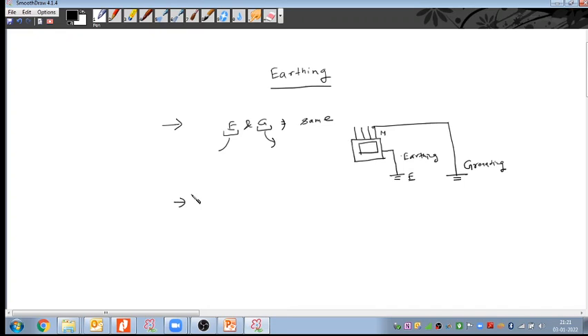Secondly, grounding, in my opinion, is what we refer to when some sort of fault occurs. For example, if any machinery, panel or motor has leakage current, or some other unwanted or unbalanced type of fault happens, then we refer to it as grounded or earth leakage ground, or neutral ground resistance. As you said, in the case of a transformer we connect a resistor of some optimum value to the neutral point. So grounding basically refers to unwanted things like fault, leakage current, or unbalanced conditions.